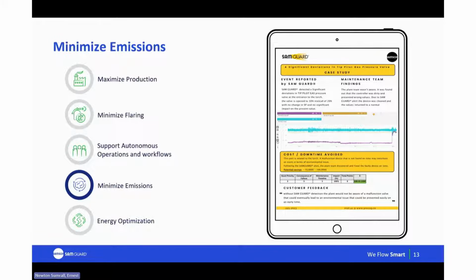Cost and downtime avoided. Well, the issue was tied to the flare system, where a malfunctioning device could have led to a significant environmental incident. Depending on how you're looking at it, it just would have burned a lot more gas than was necessary. Thanks to SamGuard's alert, the faulty valve was discovered and fixed before it escalated, potentially saving the plant tens, according to them, to hundreds of thousands of dollars. And I'm guessing that could have been in compliance. I don't know, but they were very happy with the feedback. The customer acknowledged that without SamGuard's detection, they wouldn't have even noticed the malfunctioning valve. Catching it early not only prevented a costly environmental issue, but allowed for a pretty easy and timely fix.